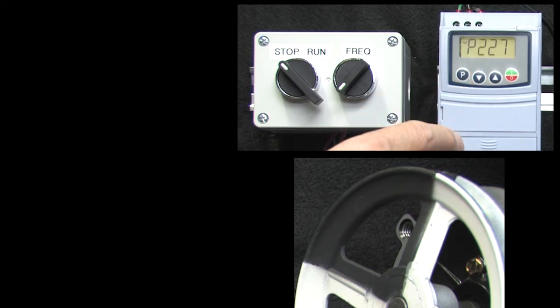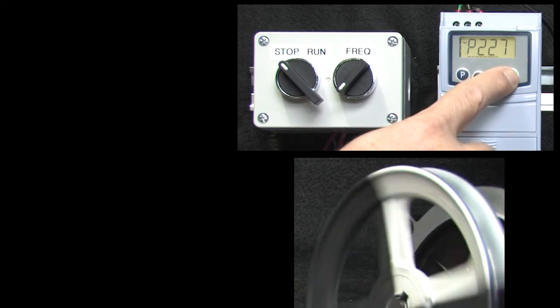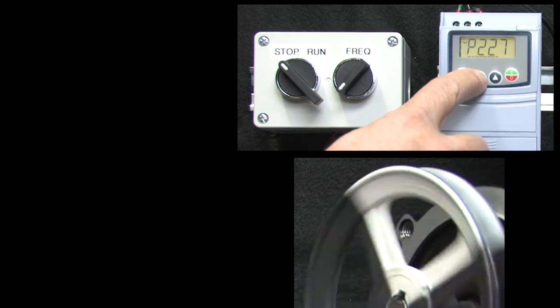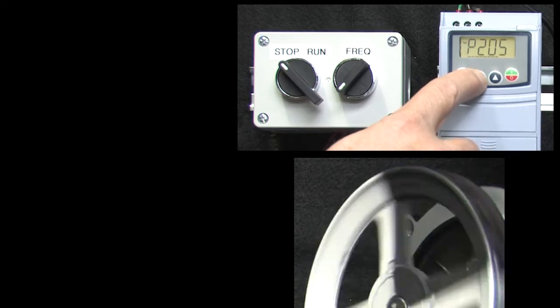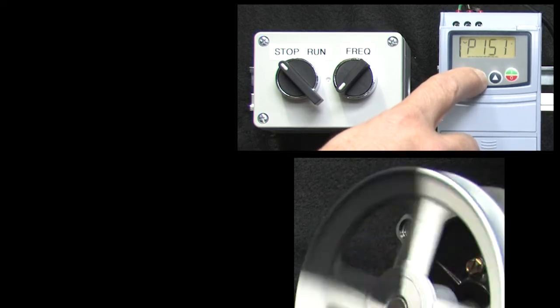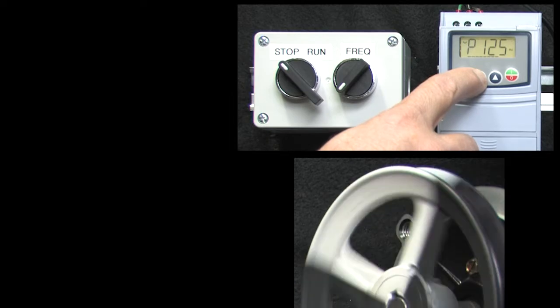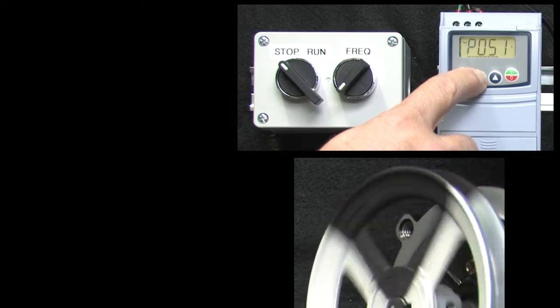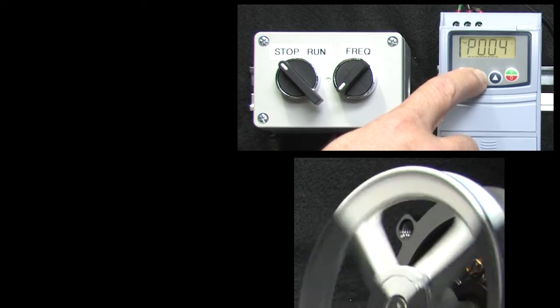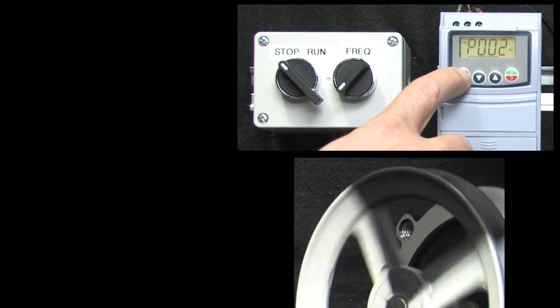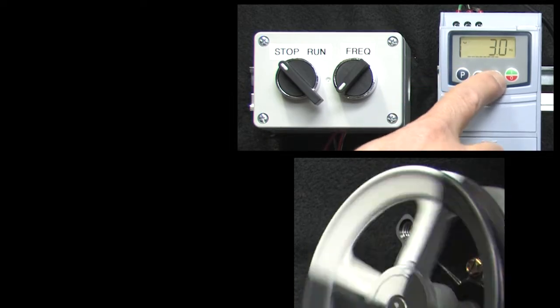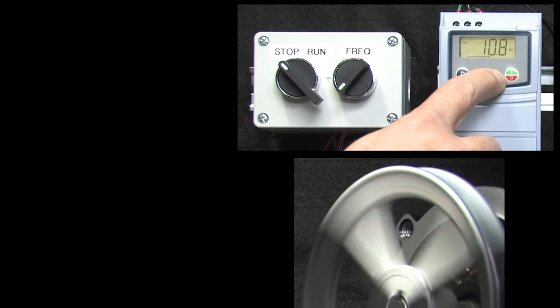Now, I am still in remote mode – we haven't changed that – but now we can control the drive from the keypad and if we scroll all the way down to parameter 2, which is the frequency for the drive, we can change the frequency from the keypad.